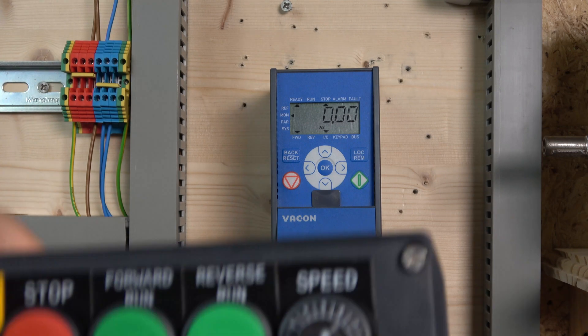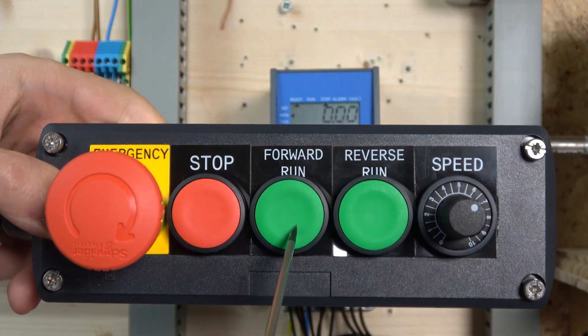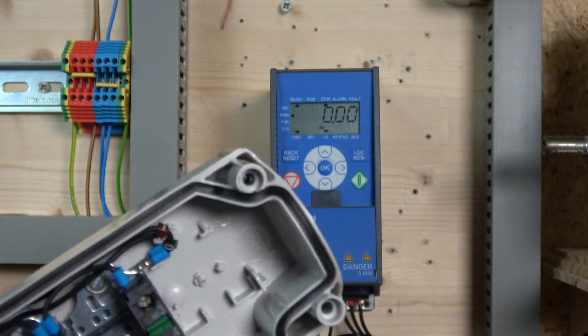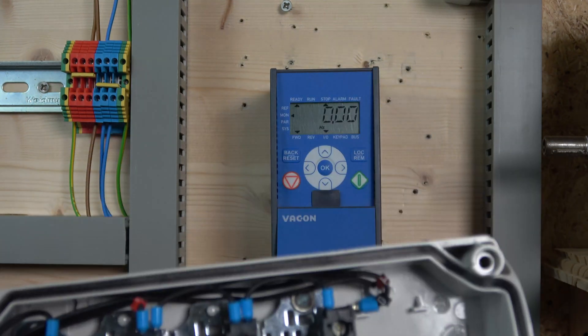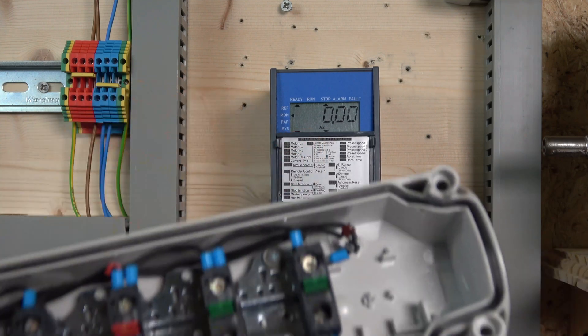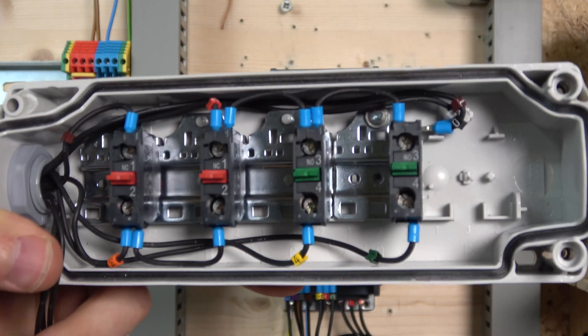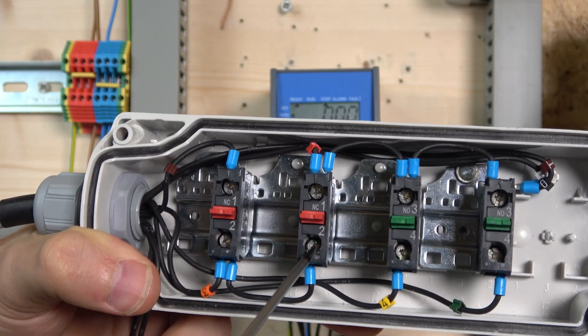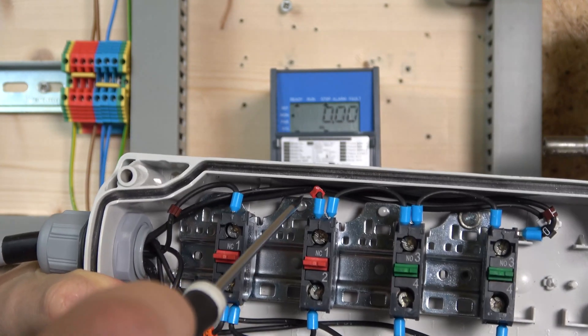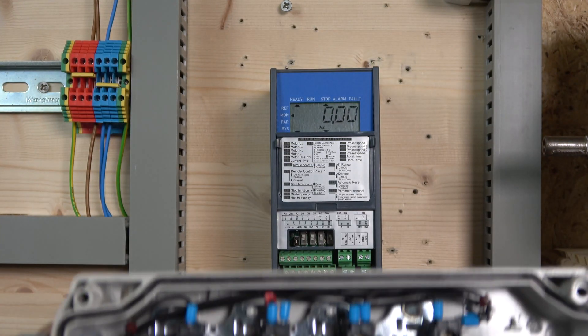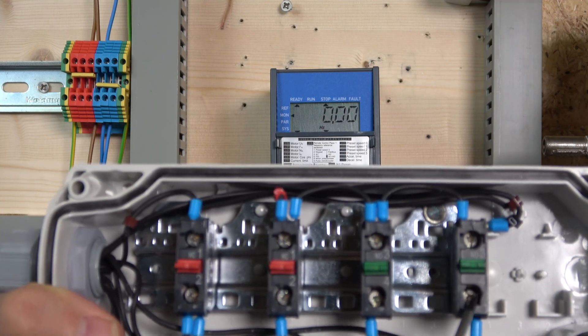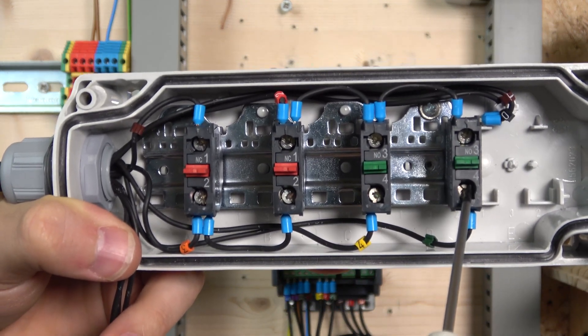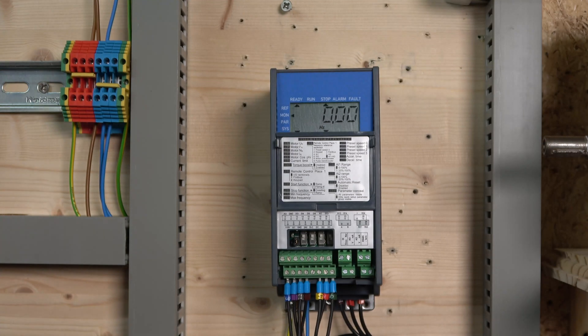For three-wire control, our station has stop, run forward, run reverse, and speed controller. Speed control stays the same as before. We're using digital inputs 1, 2, and 3. The 24V signal goes to the e-stop, then from the stop signal - wire number 2 - goes to digital input 2. Start signal goes to digital input 1, and reverse start goes to digital input 3.